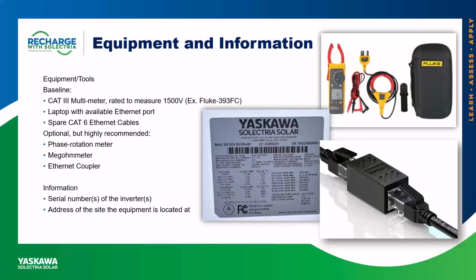Next, we have the optional pieces of equipment. Again, we highly recommend these be brought to site, but as you can see, we additionally recommend a multimeter capable of testing diodes, an example being a Fluke 87V, a phase rotation meter, a megohm meter, and an Ethernet coupler. For the items listed under the optional category, while technically not needed to provide basic information, as we will discuss when we get into the actual codes, these pieces of equipment can be used to alleviate potential revisits and in turn reduce downtime for the inverters.